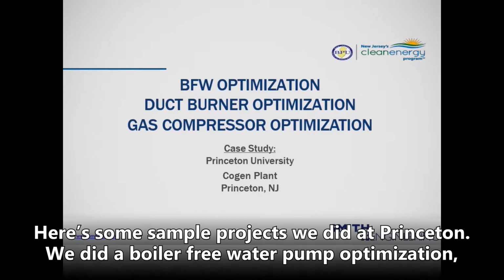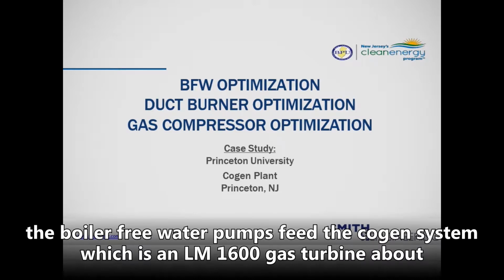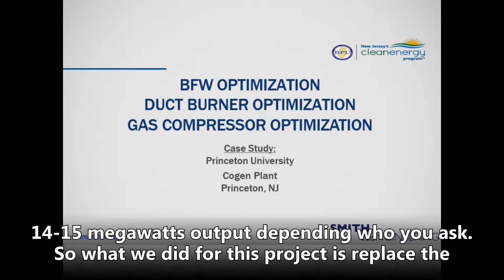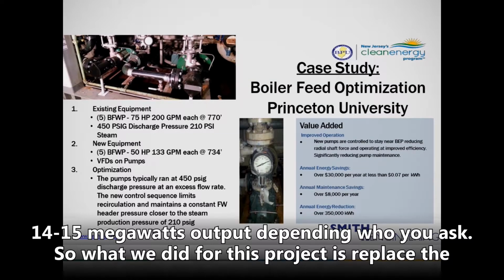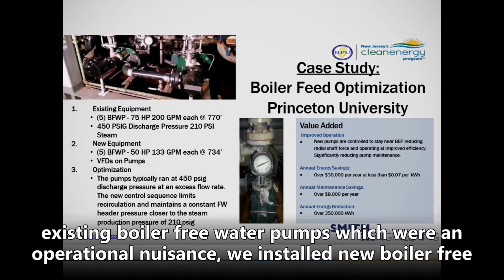So here's some sample projects that we did at Princeton. We did boiler feed water pump optimization. The boiler feed water pumps feed the cogen system, which is an LM 1600 gas turbine, about 15 megawatts of output, depending who you ask. GE 15, obviously.